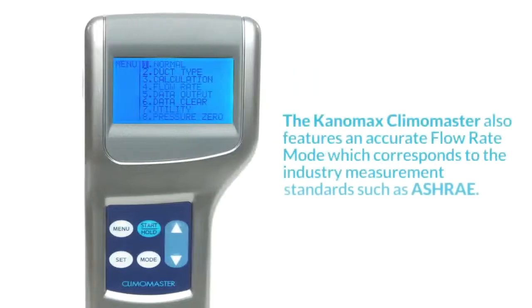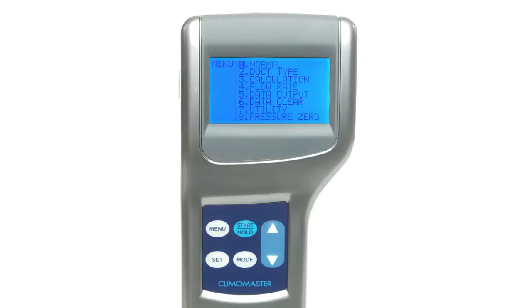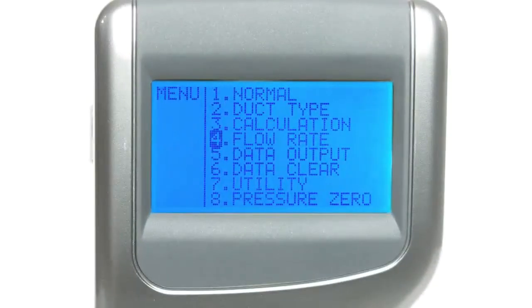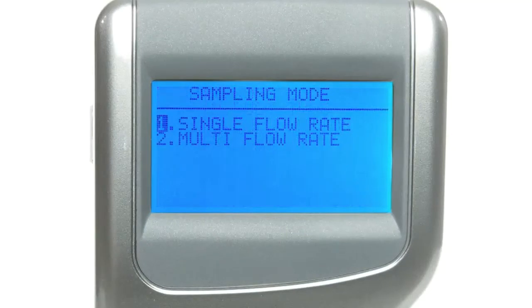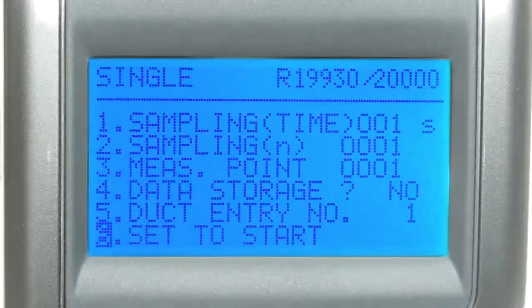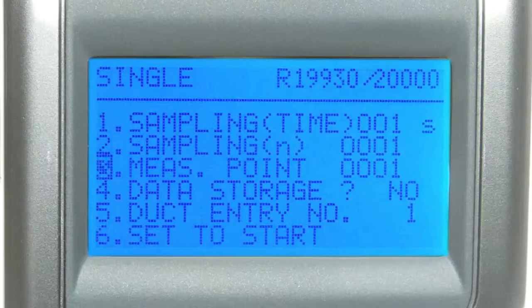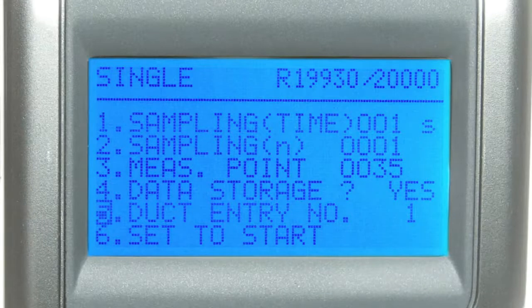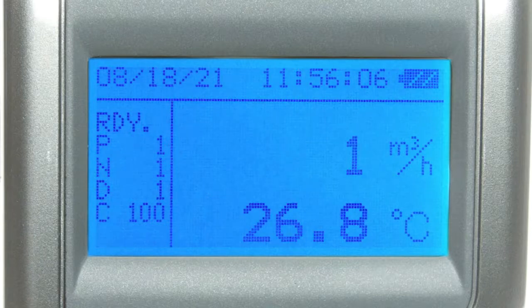The Kanomax Climomaster also features an accurate flow rate mode, which corresponds to the industry measurement standards such as ASHRAE. This mode is useful for performing a measurement of the airflow of ductwork. From the main menu, select Flow Rate. Under this section, you have the option of choosing single or multi-flow rate. Select single. On the next menu, configure your setup similar to how you would in calculation mode. This time though, you'll be configuring how many measuring points you want to include in your measurement and which numbered duct entry is being measured. Once you have everything set to your liking, select Set to Start to be brought to the ready screen.